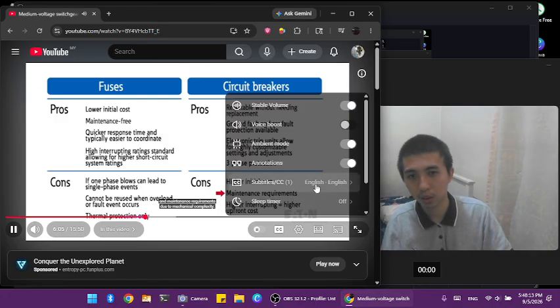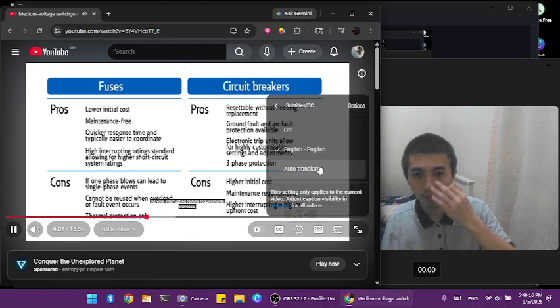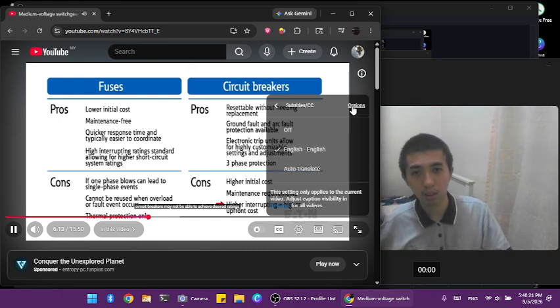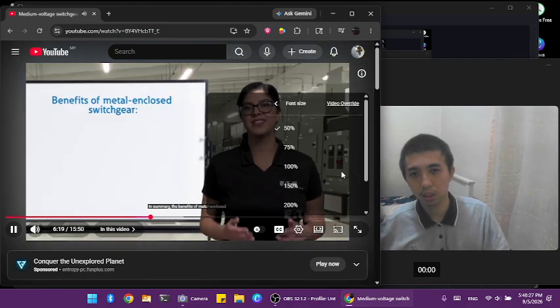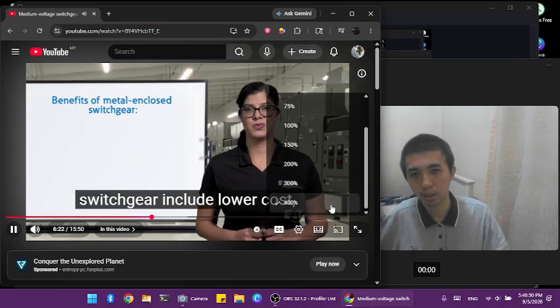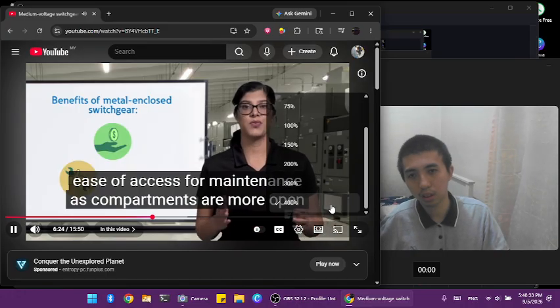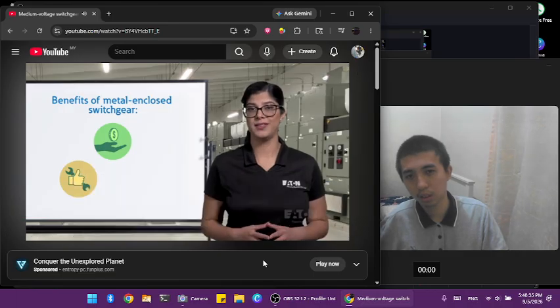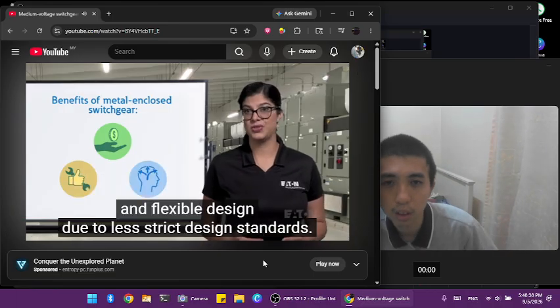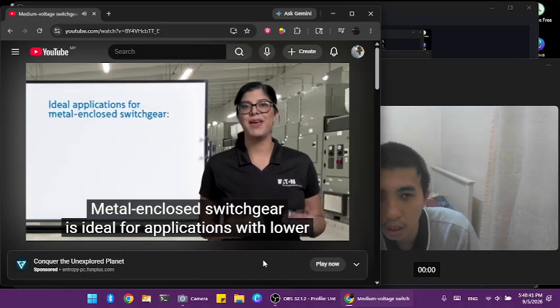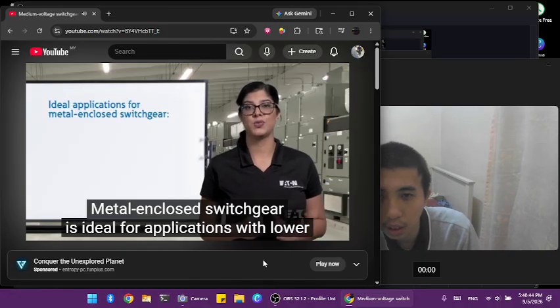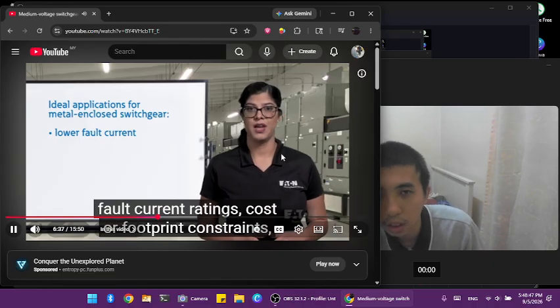However, with a circuit breaker, you're going to have higher initial cost and maintenance requirements due to mechanical complexity. As your interrupting rating requirements increase, circuit breakers may not be able to achieve desired ratings or may be cost prohibitive. In summary, the benefits of metal enclosed switchgear include lower cost, ease of access for maintenance as compartments are more open, and flexible design due to less strict design standards. Metal enclosed switchgear is ideal for applications with lower fault current ratings, cost or footprint constraints.